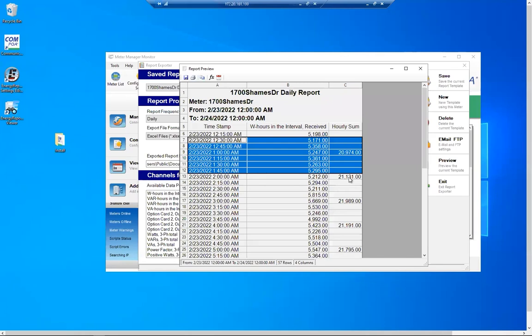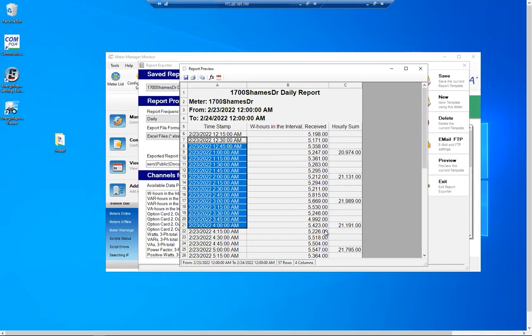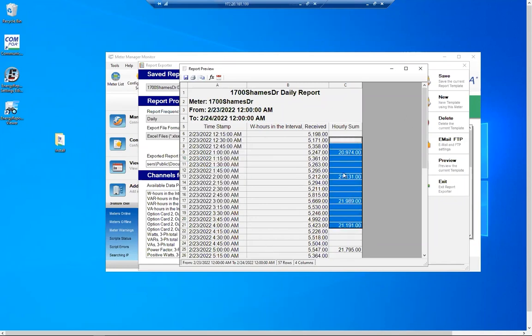Related to that, the third question is how do we deal with zero padding? We don't. There's no zero padding in Report Exporter. It just puts in blank cells or no lines for a timestamp. So with Report Exporter, if you're doing automatic processing on it, it's important for your processor to look at the timestamp. It's there for a reason, and then cross-reference that with the value.